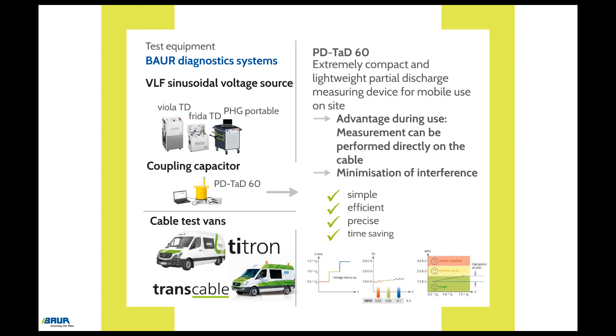Checking cable routes with the PD-TaD 60 is simple, efficient, and precise. It also saves time because the dissipation factor measurement and partial discharge testing are performed in parallel. A comprehensive checking of newly laid or repaired cables, as well as general condition evaluation, can therefore be performed quickly and simply in a single operation without significant extra expense. This means that the cable only has to be loaded with the test voltage once. Cable testing and diagnostics with Baur measuring devices can be used for the testing of both new and worn cable routes, whilst adhering to all relevant standards.